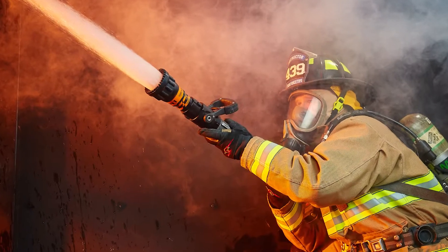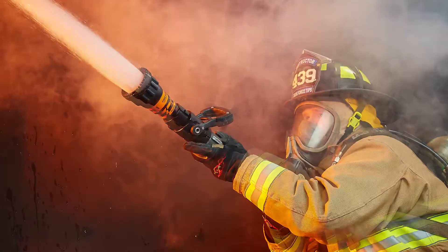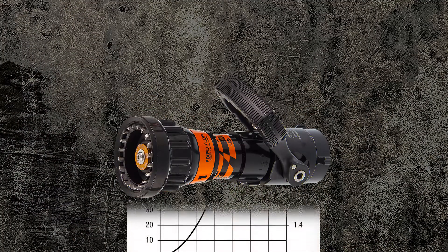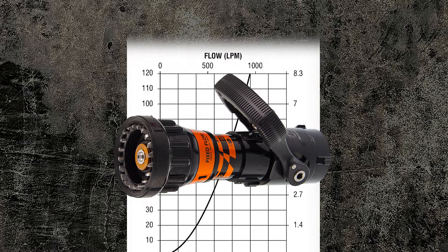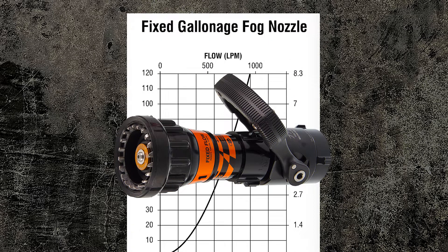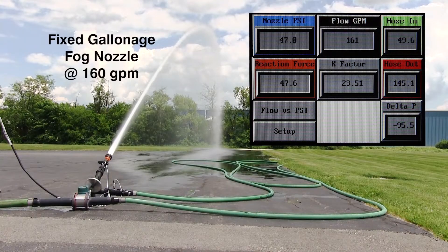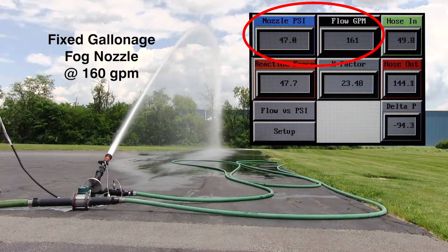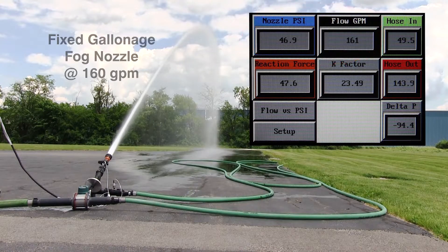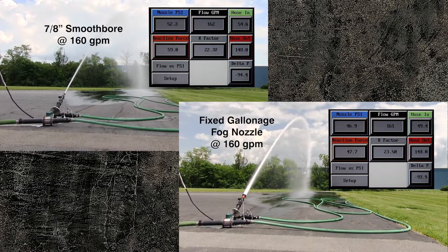In this episode, we will use a fixed gallonage fog nozzle and show that not only does it follow the exact same curve as the smoothbore, but that the same formula can be used to calculate flows and pressures. Here, the fixed gallonage fog nozzle is flowing at about 160 GPM at about 50 PSI. As you can see, the 7/8 inch smoothbore and the fixed gallonage fog nozzle are flowing almost identically to each other.